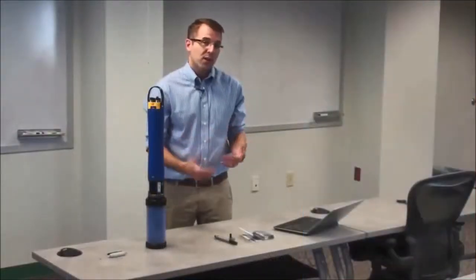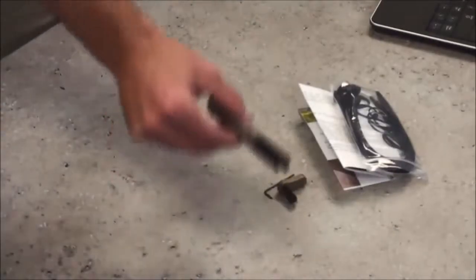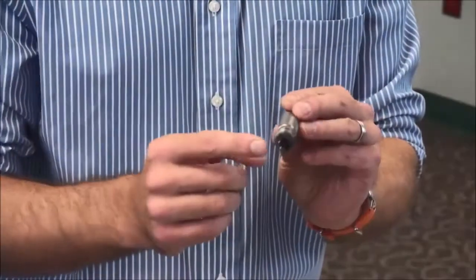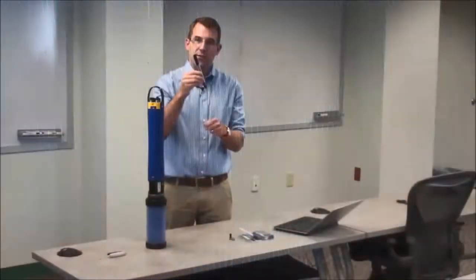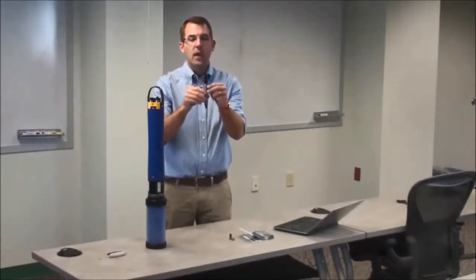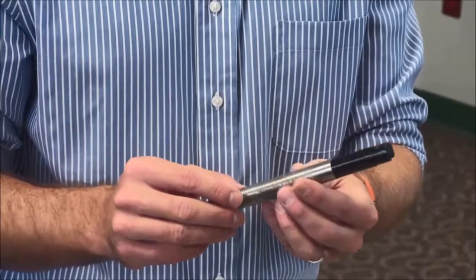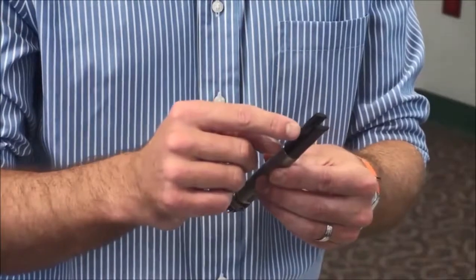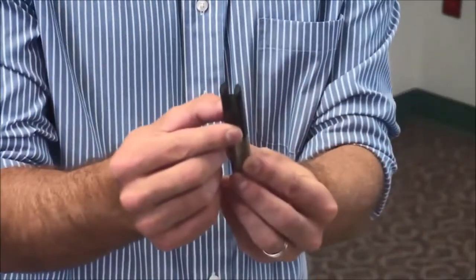Taking a look at what comes with your wiped conductivity probe is the sensor itself, with your wet mate connector that allows you to just plug and play the new sensor inside your existing sonde. The conductivity temperature cell. Note the temperature is actually inside this black housing, and the conductivity cell has a groove here that allows the wiper brush to pass through.